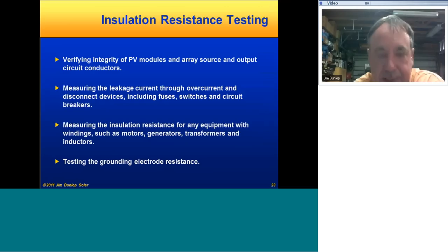Now, insulation resistance testing, interestingly enough, some of the newer inverters are doing this on startup every day, so that's going to make this job a little easier. But this basically involves verifying the integrity of the wiring system by applying a high voltage across the circuits to ground and between conductors, and verifying either by measuring leakage current or by actually measuring the insulation resistance with a megohm meter or special insulation resistance meter. And we're looking for, obviously, a low value, something less than a megohm, that would indicate some sort of fault in the system. You can also use this equipment to test the grounding electrodes in the system as well.